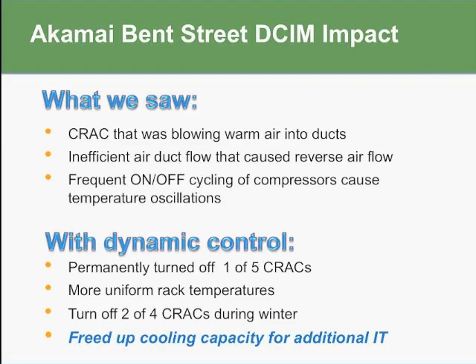With dynamic control, we were able to permanently turn off one of the 5 CRACs, the one that was actually heating, not cooling. We saw much more uniform rack temperatures, and we are now able to turn off 2 of the remaining 4 CRACs during the wintertime when it's much cooler outside. So you can imagine the amount of energy and money that we saved in those situations. And furthermore, we freed up cooling capacity for additional IT. So we now have another CRAC unit that we could turn on if we wanted to, making sure it's now cooling rather than heating, if we wanted to take on more IT equipment. And for someone who's in the business of colo, that could mean you're taking on more colo clients, which is more revenue for you if you're effectively increasing your cooling capacity by optimizing the cooling equipment and operations.